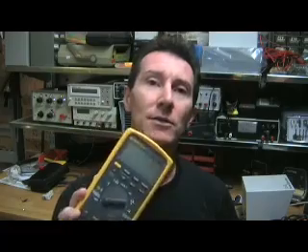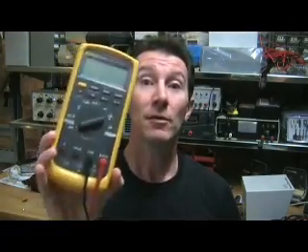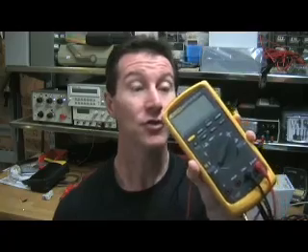Most people think the burden voltage drop is really small, but it's not. The closer you get to the full scale range of the meter, the bigger the drop. A really good meter like the Fluke 87V will have — well, this one actually has 1.8 millivolts per milliamp burden voltage. So if you pass 200 milliamps through this, if you try to measure 200 milliamps, that's a 360 millivolt drop.